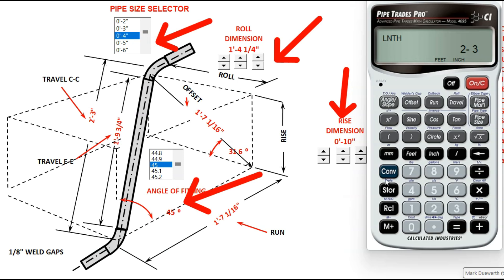So with the calculator, always convert clear first. We're going to put in the pipe size first — 4 inch pipe size. We're going to tell it 45 is our angle of fitting. We're going to put in 1 foot 4 and 1 quarter inch and enter that as our roll. Now for the 10 inches, because it's a rolling offset, you've got to activate convert rise, because above that is the roll key.